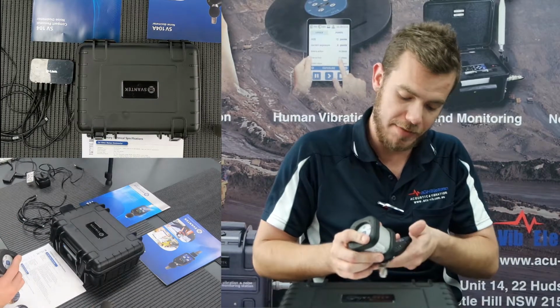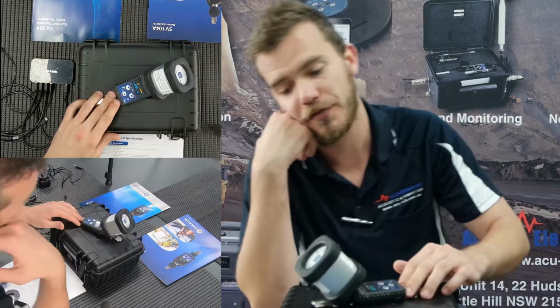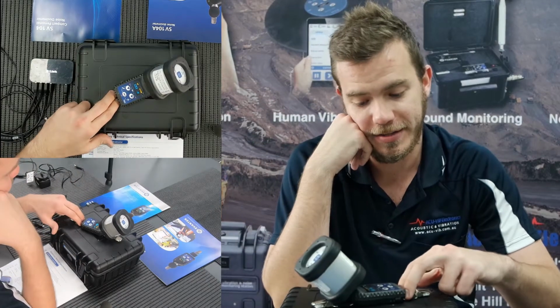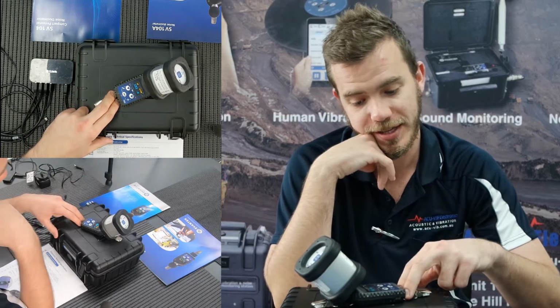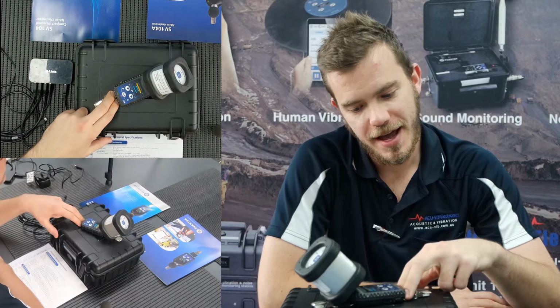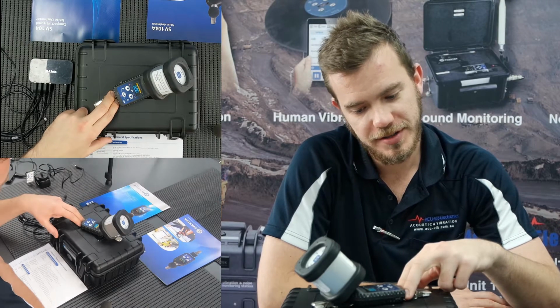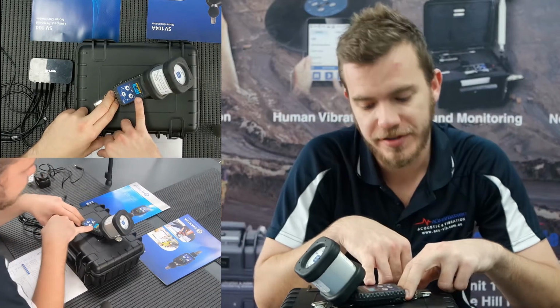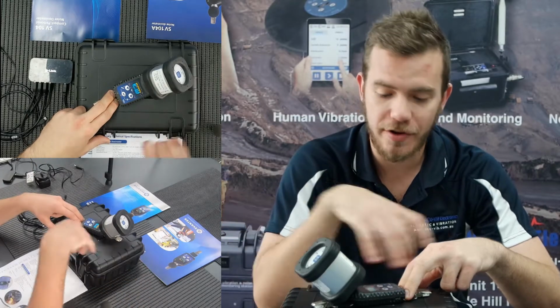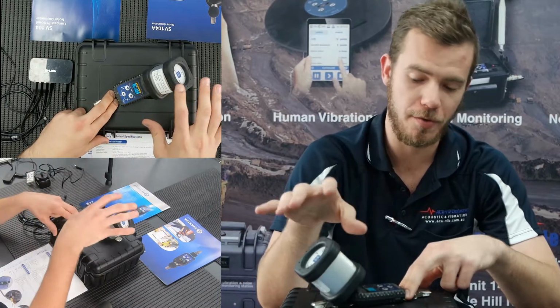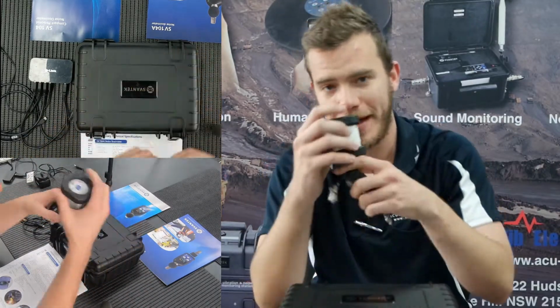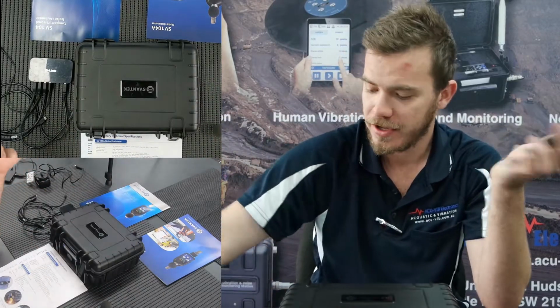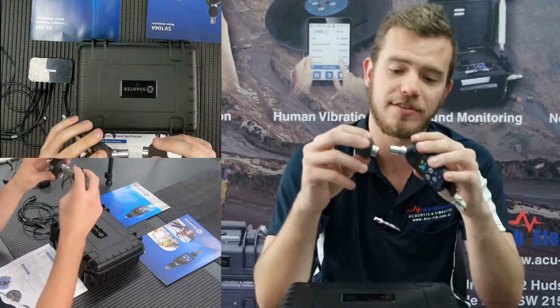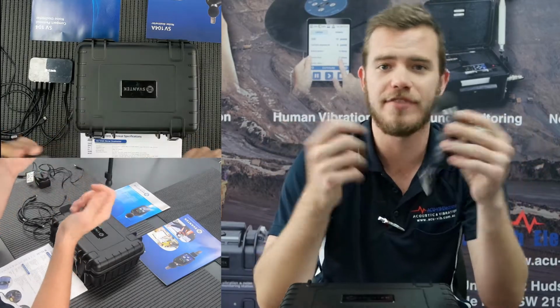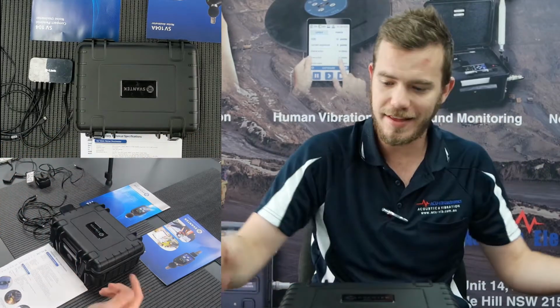And just one more time, let's see what happens. So let's plug in 114 dB. We're going to wait for the instrument to sense the level in the acoustic calibrator. Here we go. So the delay and the auto calibration is coming. And now you can see it's 0.04. So me tapping that microphone has had no impact on the drift of the microphone, which just proves that the MEMS solution is, you're going to save money on constantly replacing mics, and with the lifetime warranty, you can't go wrong. Anything else in the kit?